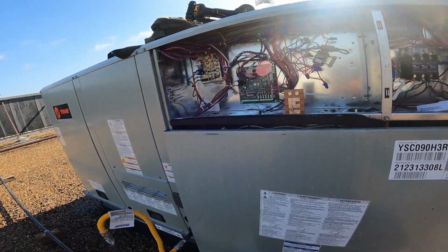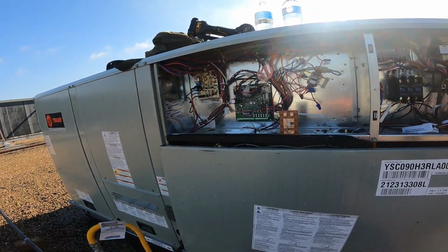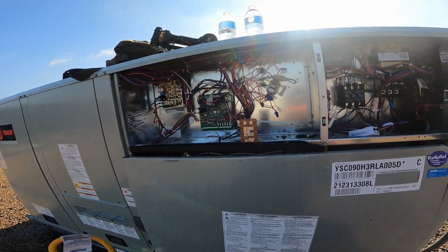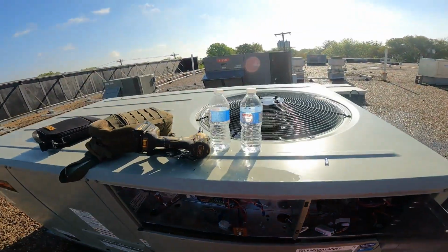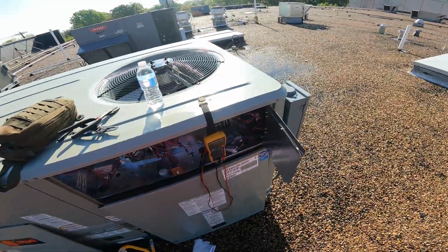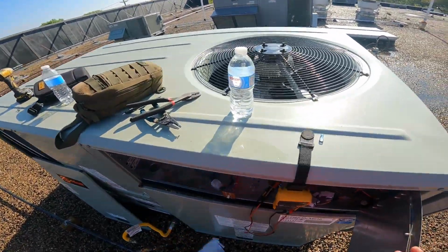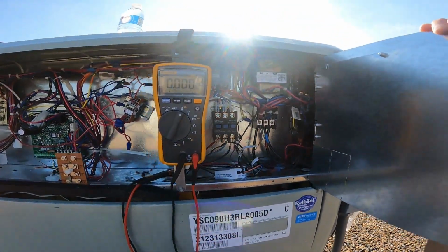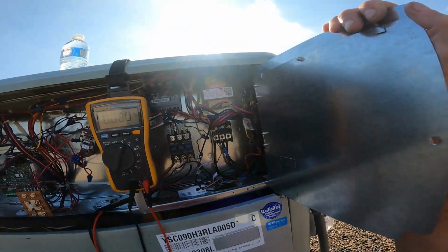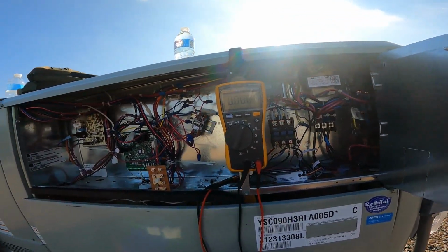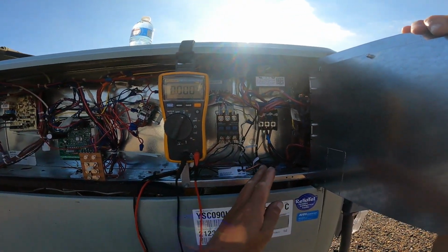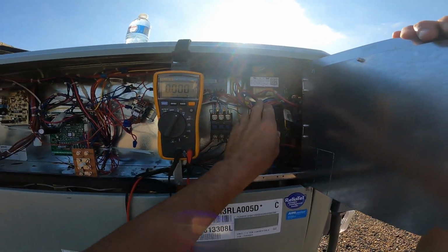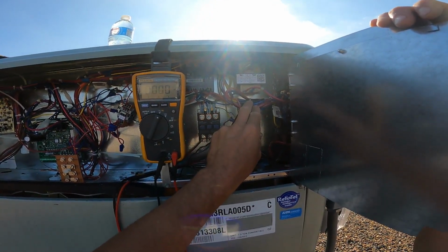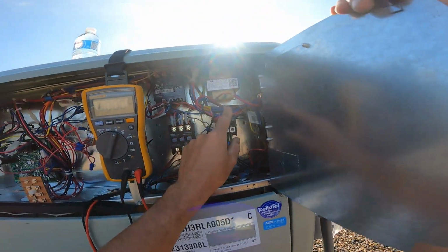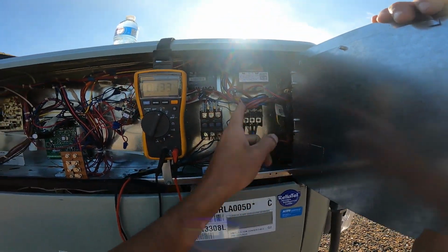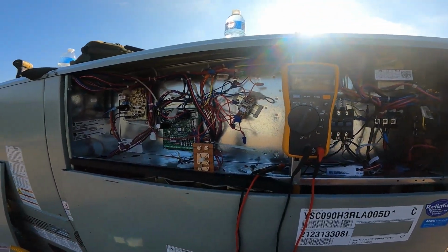What else happened? What else happened? So I had to answer a couple messages. The only other thing that I did was... what did I do? I checked the voltage to make sure we're not dropping the leg, and I checked the transformer incoming voltage because we want to make sure the transformer is on the right setting. This transformer has a 208 setting and a 230 setting. This is 208, so that is set correctly.